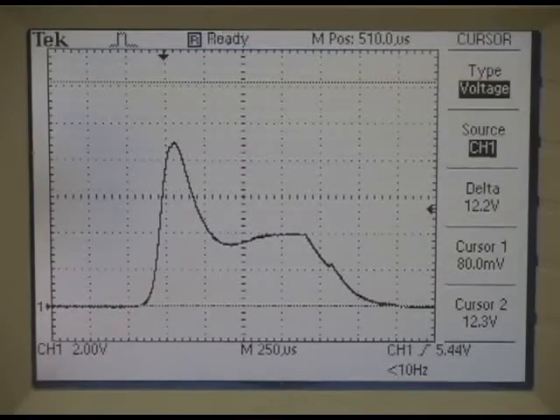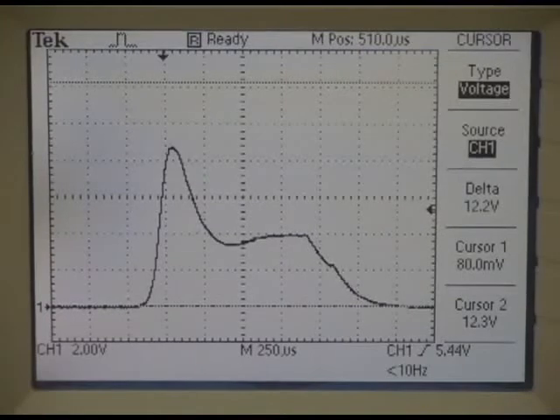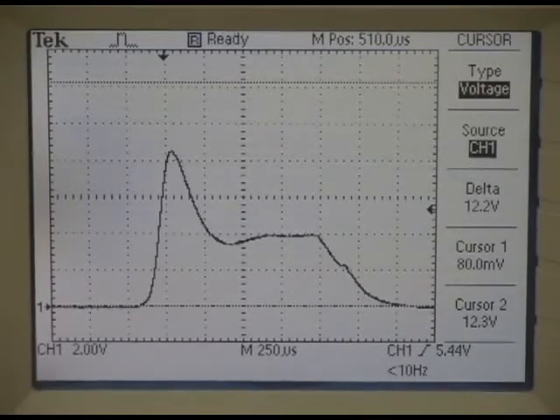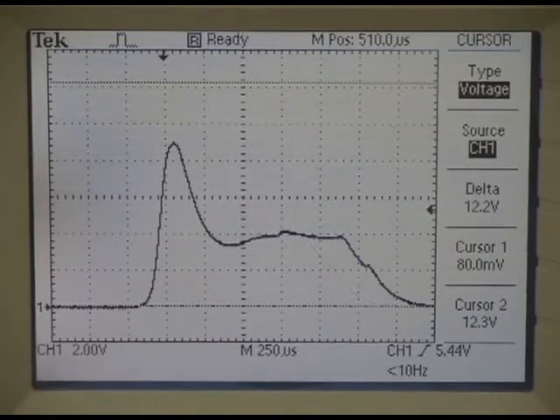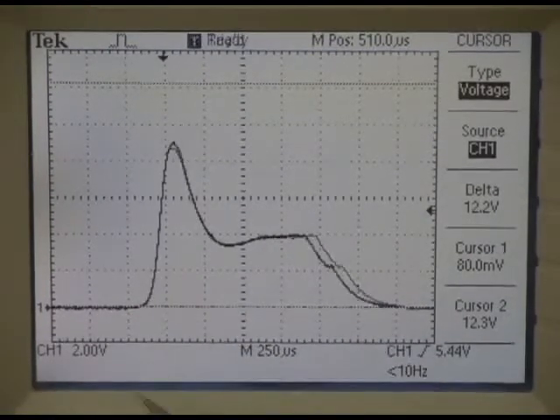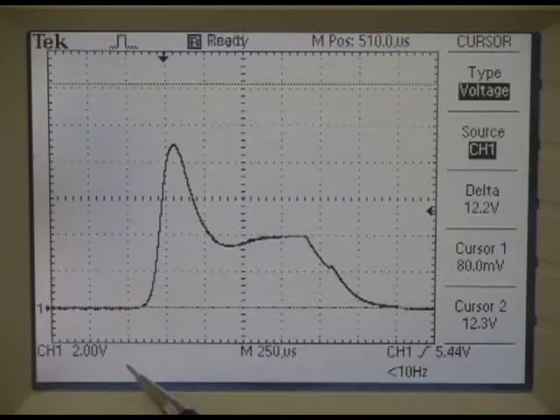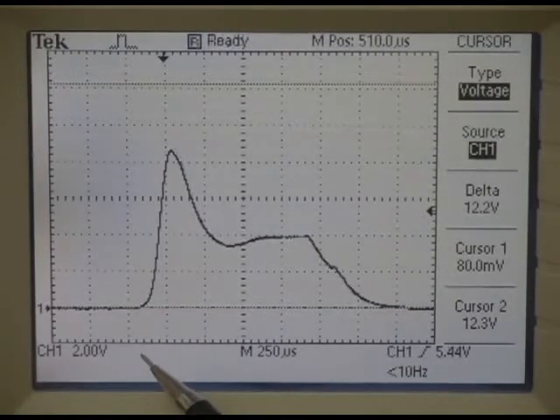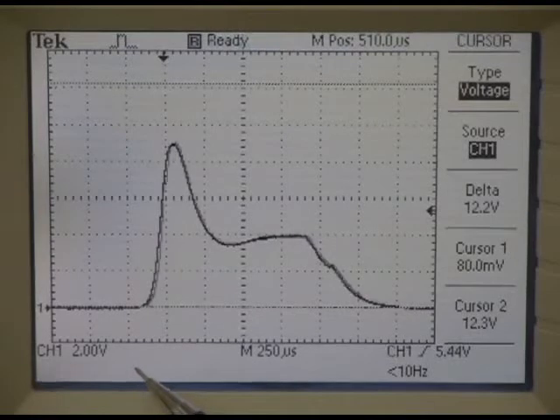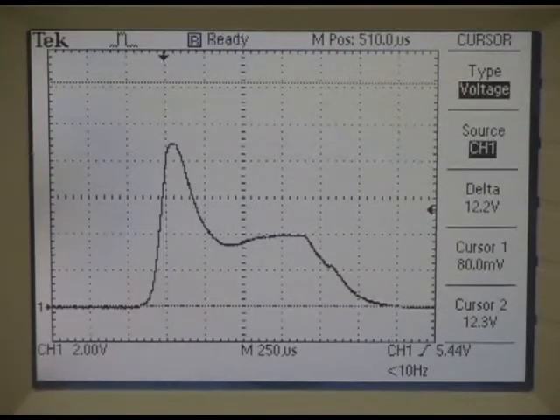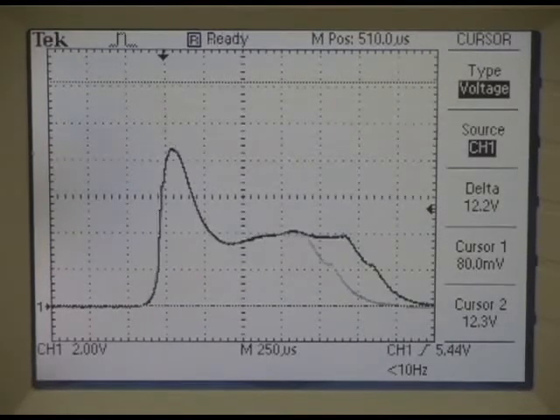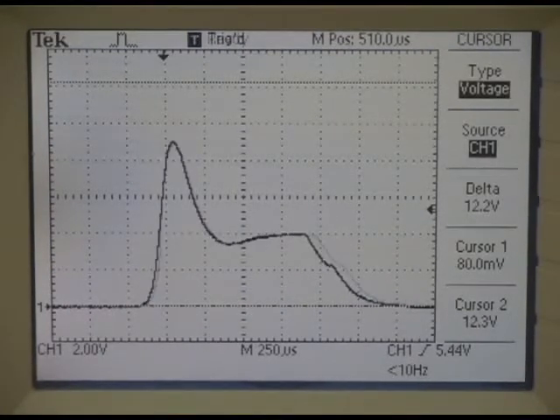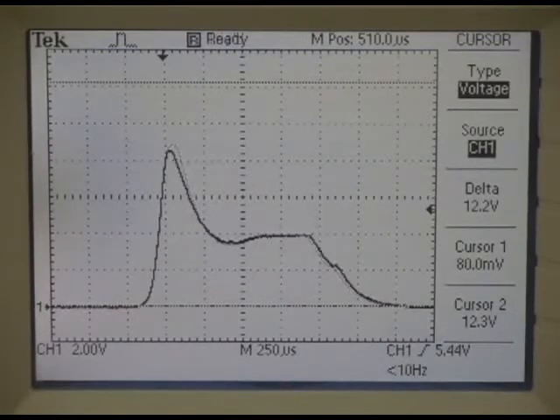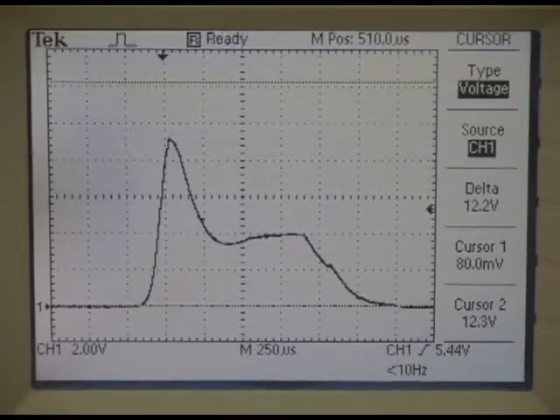So for setup today, we have the probe set on the wide range mode. So we'll go down to 1 microamp measurements up to as much as 400 milliamps. As you can see, we have our scope set for 2 volts per division. So essentially we're looking at 2 milliamps per division here, 250 microseconds per division on time scale. And see, this device wakes up approximately once every second, does a little housekeeping and goes back to sleep.